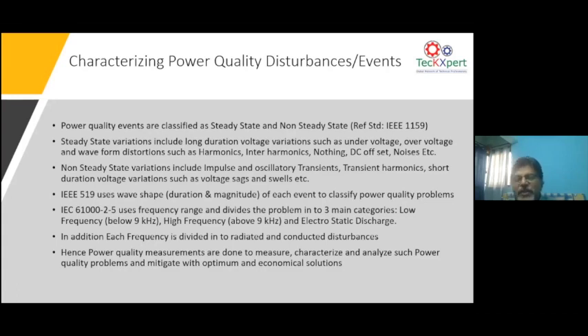When I say transient harmonics, sometimes you will have resonance happening in the network, because at the end of the day, the network has capacitor banks and transformers, and the network also has its own natural frequency. So when an impulse strikes the network, it can oscillate at that natural frequency. And if that natural frequency matches the harmonics present in the network, it can create a transient harmonic overvoltage. That reflects as an overvoltage on the grid. So non-steady state variations are well explained.